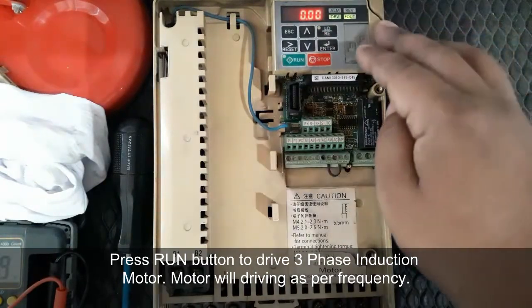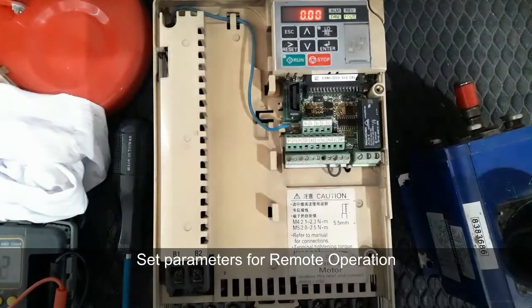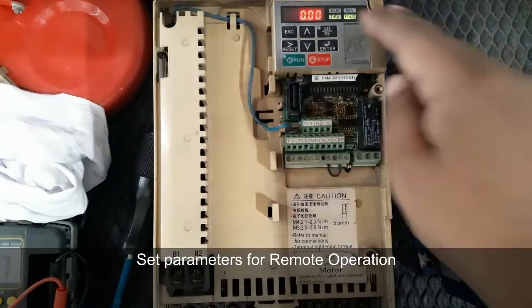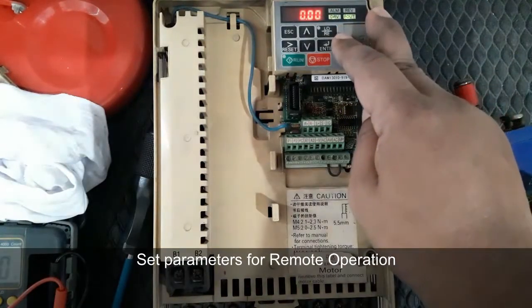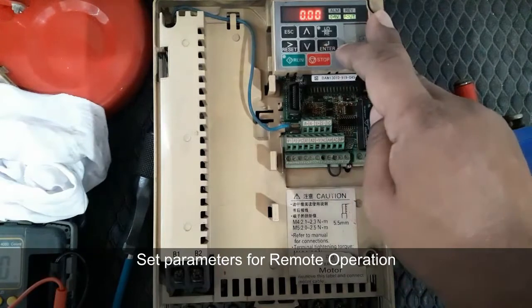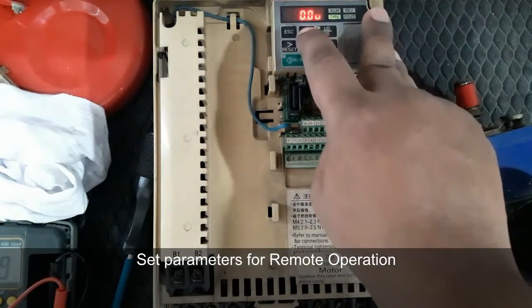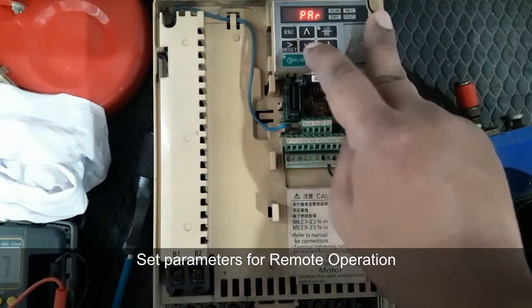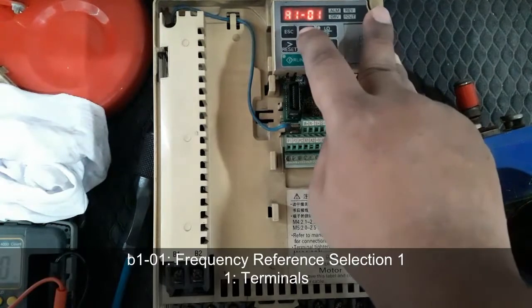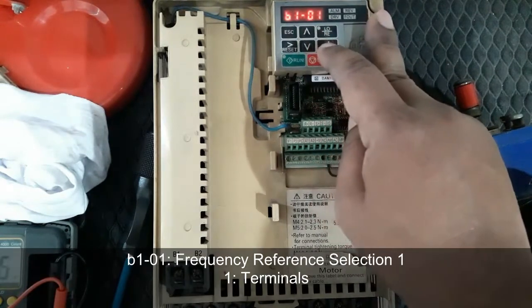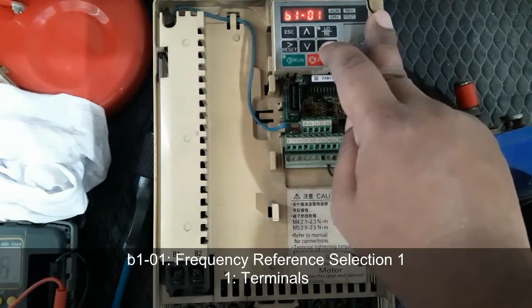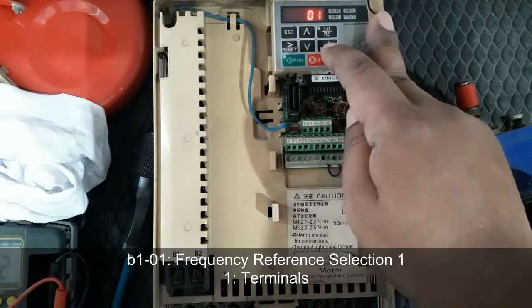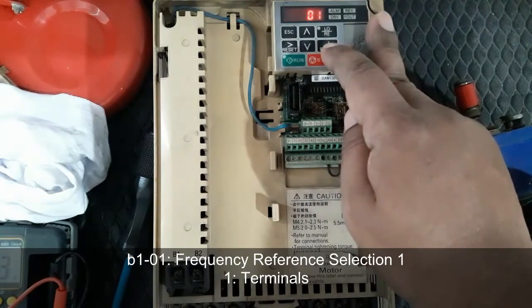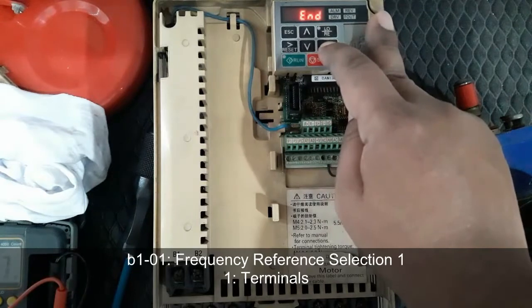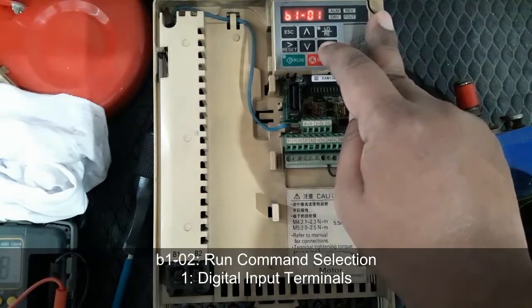The local remote button is deactivated by pressing it. Now the run command does not work. We want to set up parameters for remote operation for machine connection. So enter into parameter B101 for frequency reference selection. We want to set terminal connection here, so set 1. Press enter for saving the parameter.